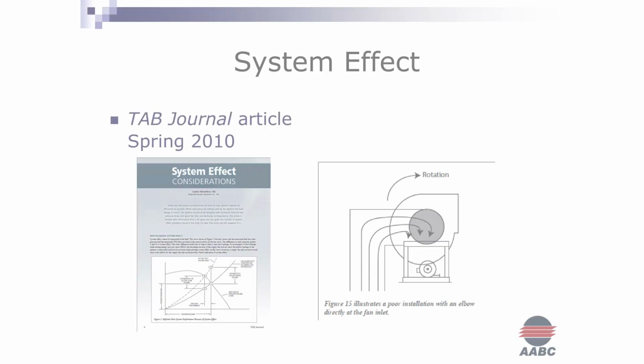And it all goes back to possibly added elbows. Maybe they got out to the job site and there was a conflict in height between the drawings and the sheet metal and the pipe, so they had to do something different to get that in. Those are the types of changes that take us away from the original design that can have an impact and actually add up to system effect.